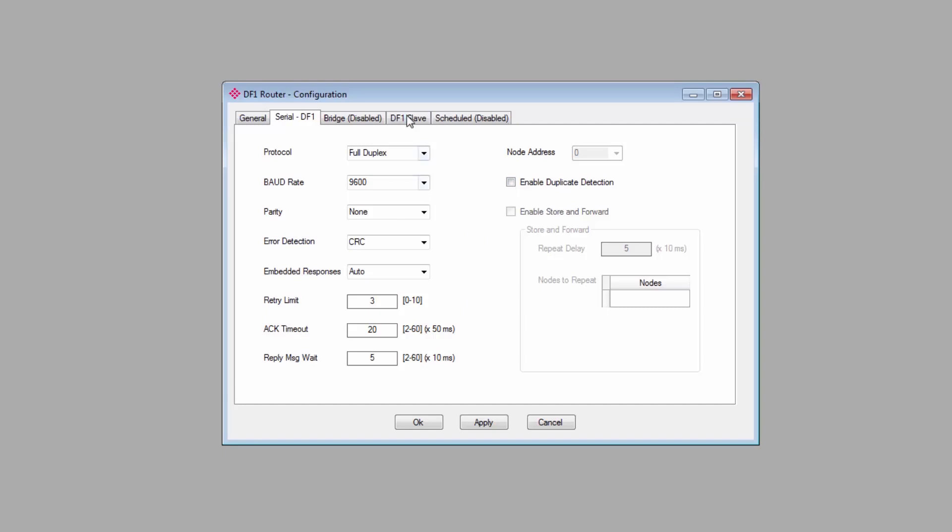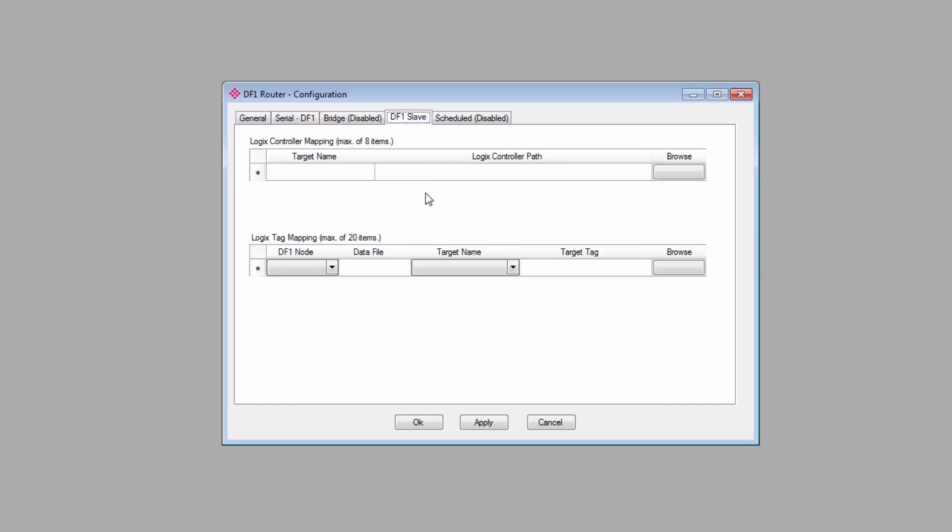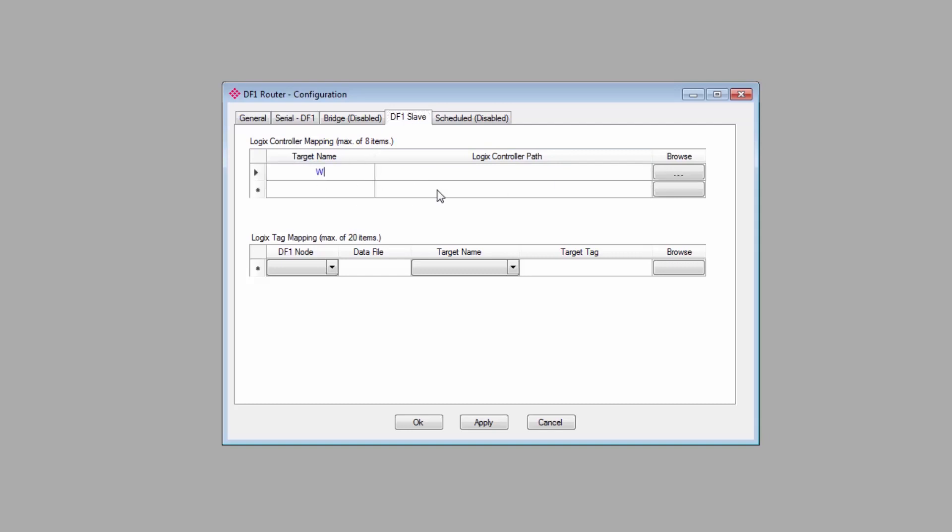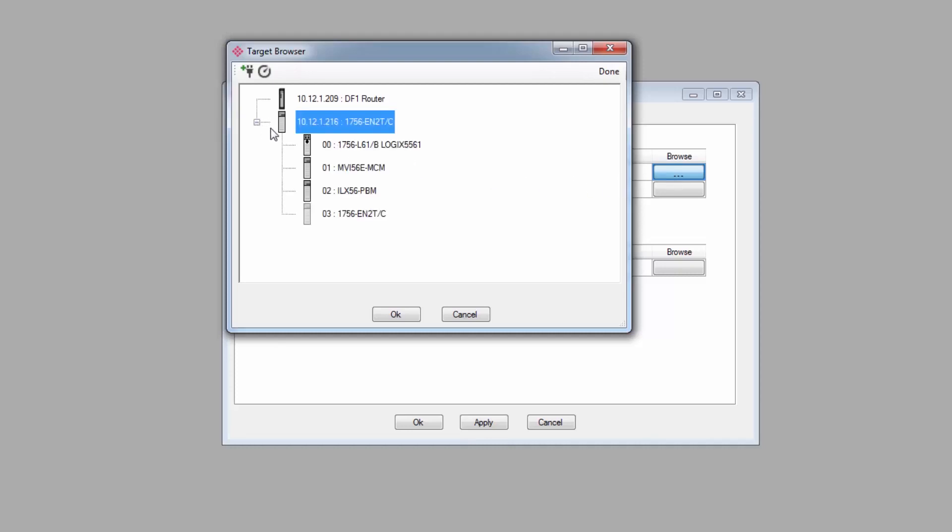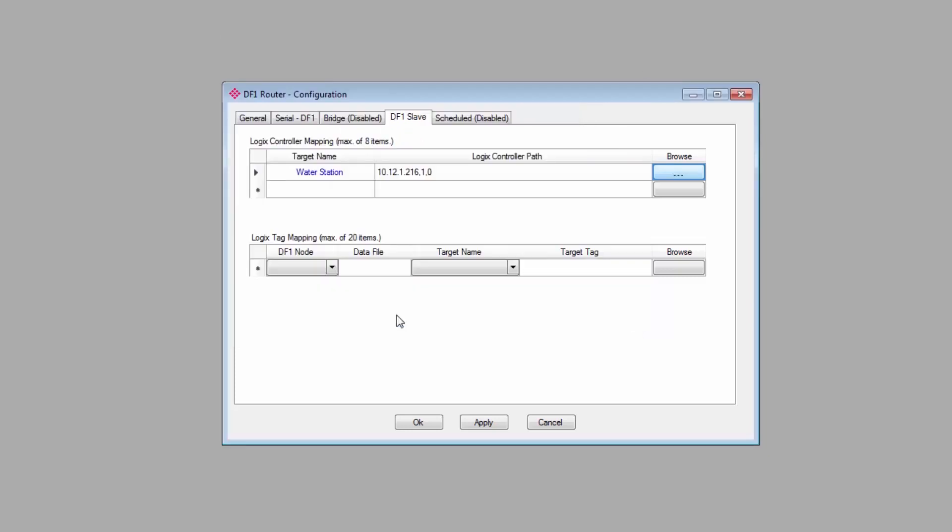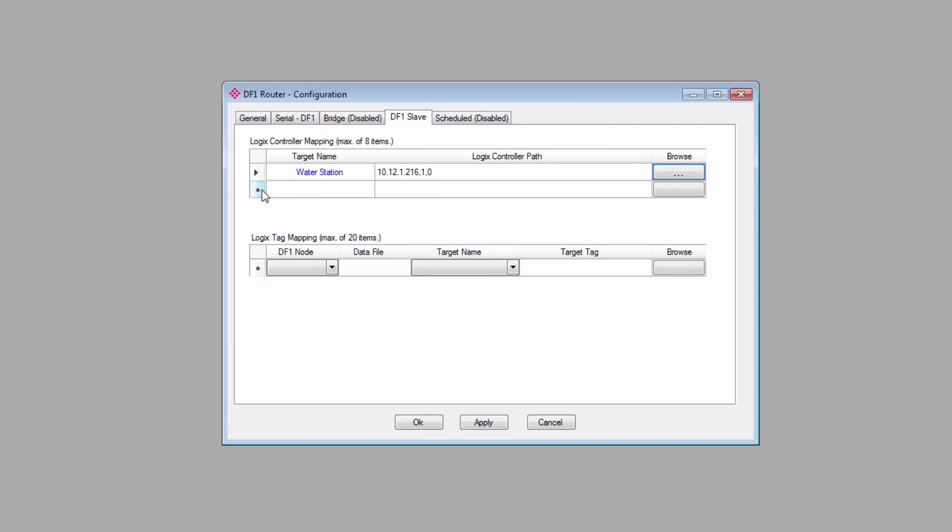Now we'll move on to the DF1 slave tab. Under Logix controller mapping, you'll select the Logix controller on the Ethernet side that you want to connect to. Give it a target name that will help you identify it. I'll name mine Water Station. Click the Browse button to use the target browser to select the controller that you want. Click OK, and its IP address will appear in the field. If you have more than one controller you want to map, you can go ahead and add up to eight.